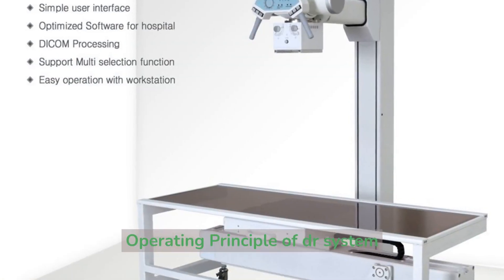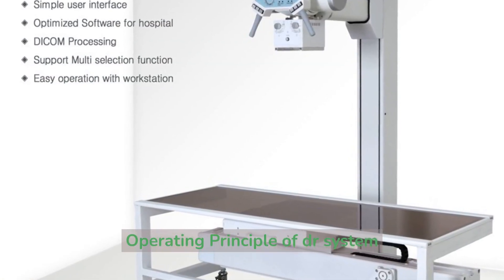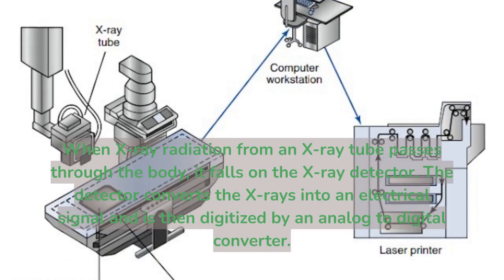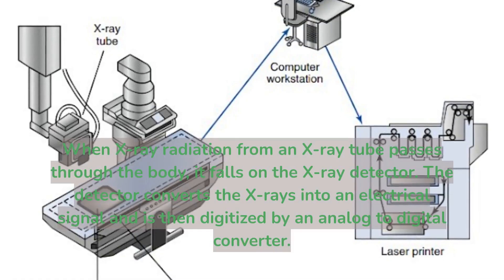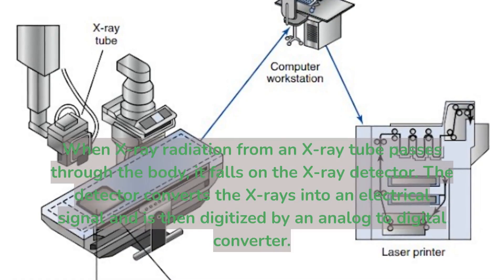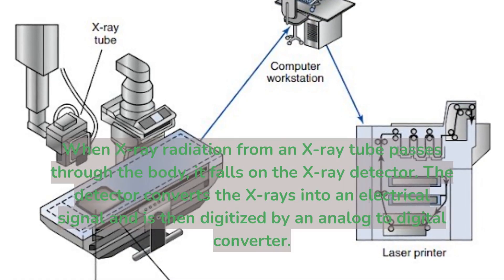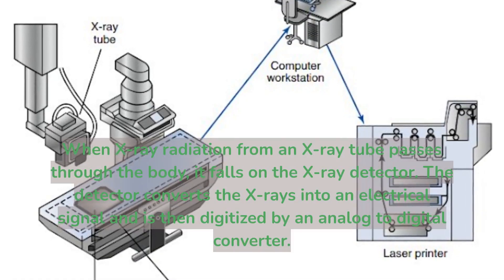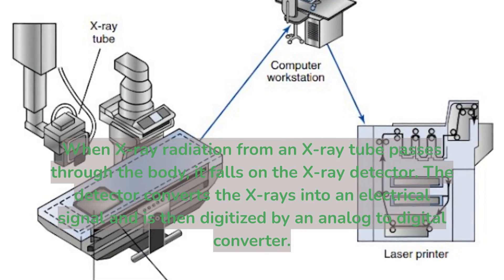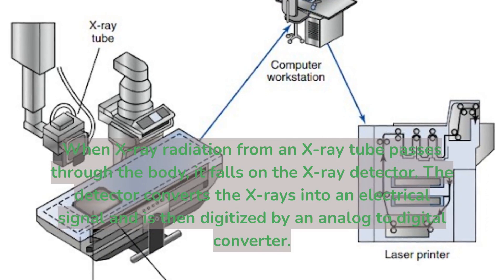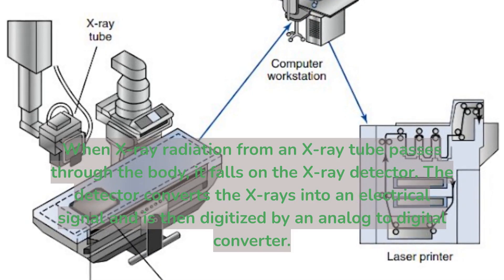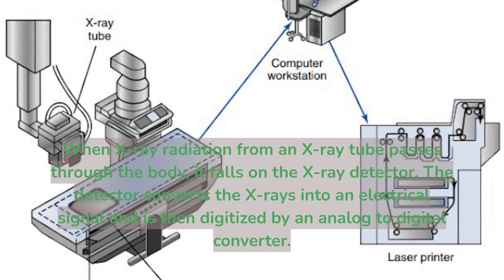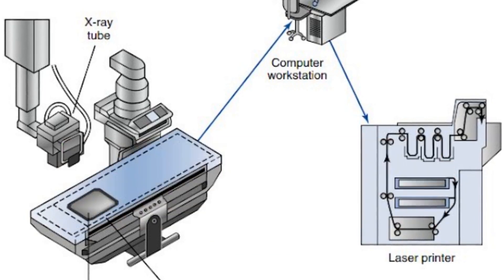Operating principle of the DR system: when x-ray radiation from an x-ray tube passes through the body, it falls on the x-ray detector. The detector converts the x-rays into an electrical signal, which is then digitized by an analog-to-digital converter.